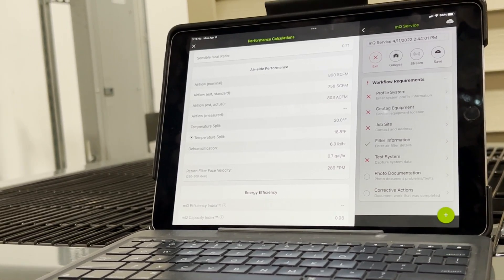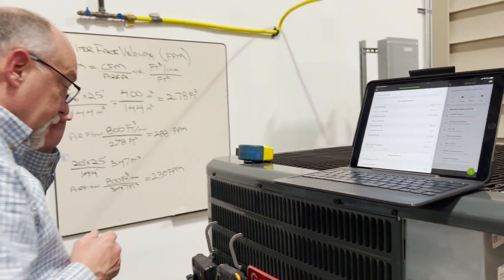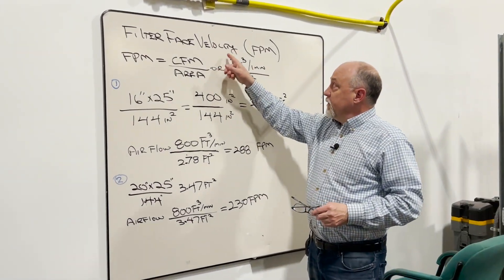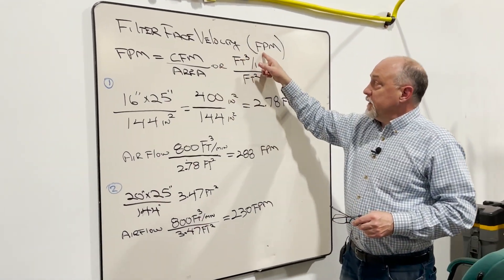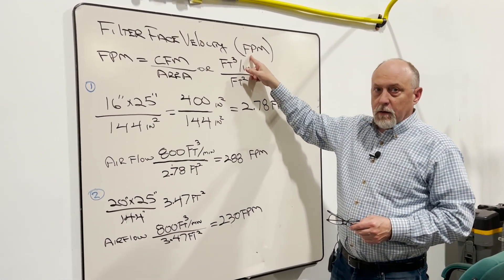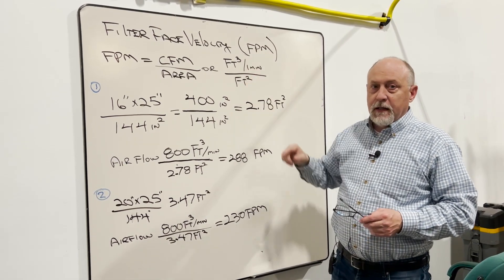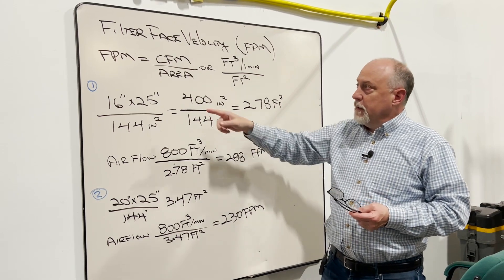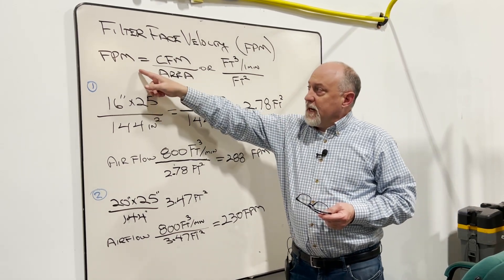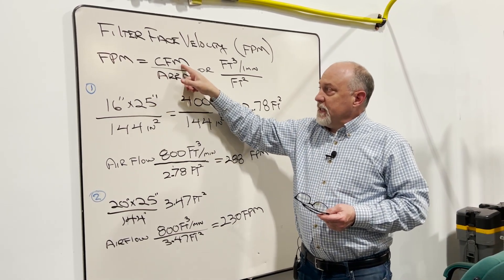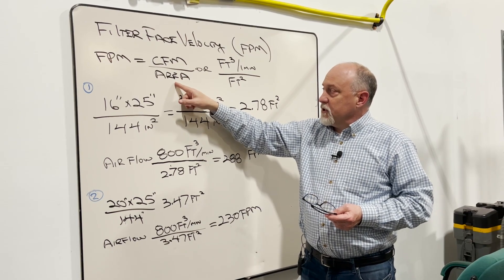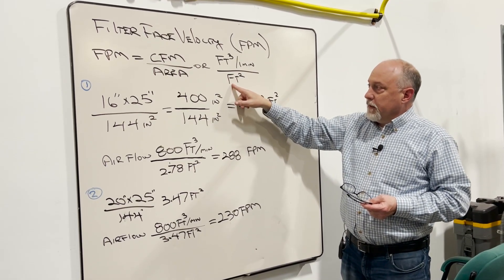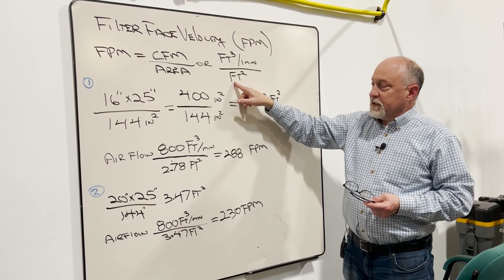Let's talk about how that's calculated. This is just a simple calculation. Filter face velocity is measured in feet per minute — that's just like miles per hour, it's the speed of the air going across the filter media. So if you want to calculate FPM, you take your CFM divided by your area in square feet. So you get feet cubed per minute divided by feet squared, which gives us feet per minute.